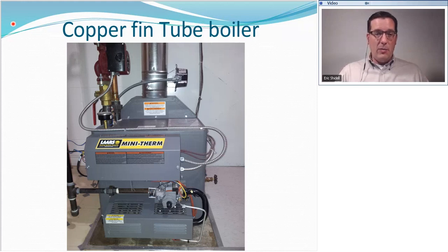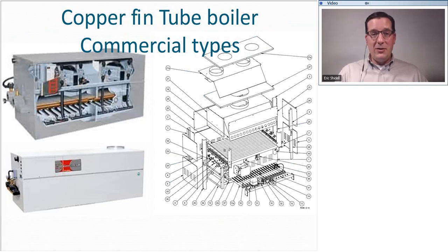And in this boiler, you can see there is the pressure and temperature gauge, and it's right next to this pipe. So that would indicate that this would be the supply, because boilers always want to be measuring the hottest water in the boiler. And so that would be the supply side, the hottest water. So the temperature sensing element is always going to be on the supply side of the boiler. So that is one kind of dead giveaway that can help you figure out which direction the water is moving if you can't read any of the labels, or it's just too dark to see, or for whatever reason. So that's one little trick that you can use.